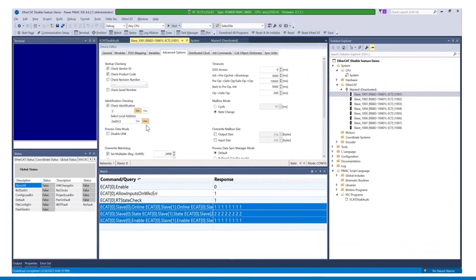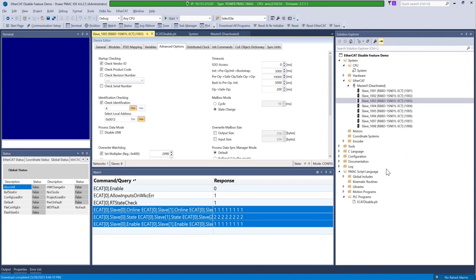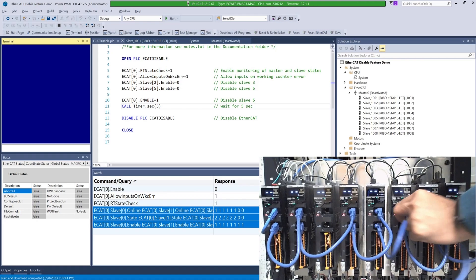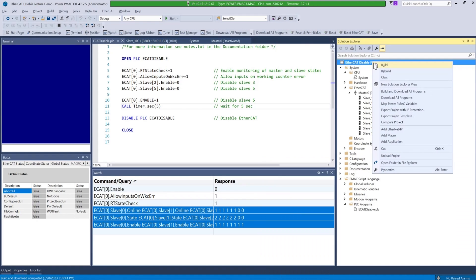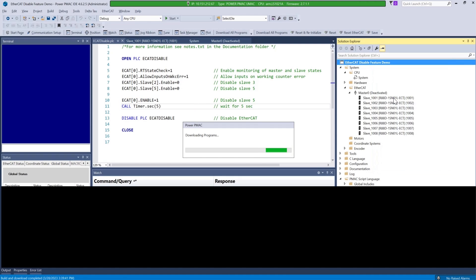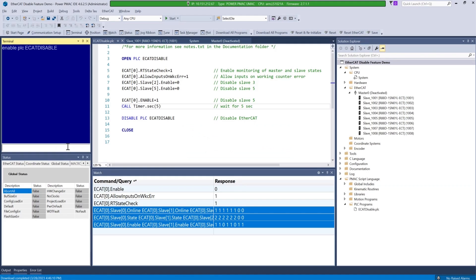So far we looked at all the parameters required to use this function. Let's apply it to the sample project. This project has 8 EtherCAT drives configured with identification checking. Now remove slaves 2 and 5 physically from the network. We will use the following PLC to set the necessary parameters: disable slave index 2 and 5, then activate the network using ECAT enable = 1. Download the project to PMAC and run the PLC from the terminal to activate the network. As you can see, the EtherCAT network is active and all devices are in operational mode except slave index 2 and 5.